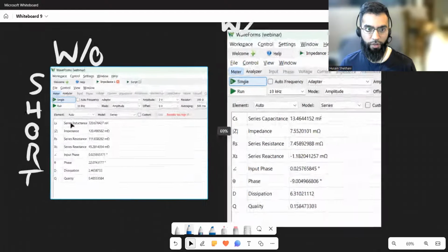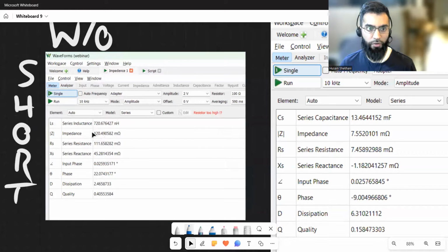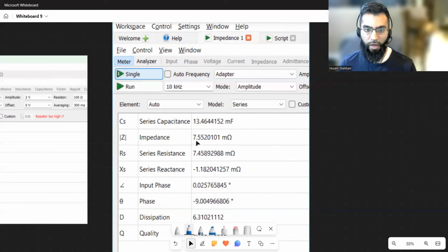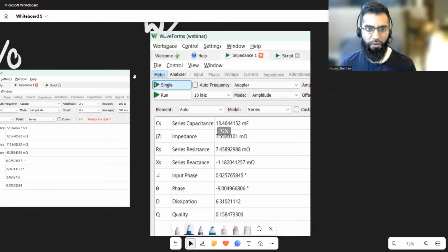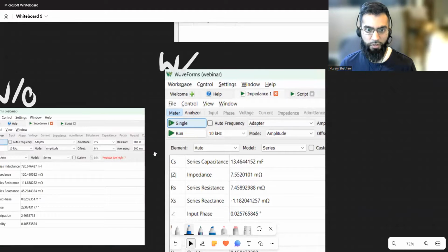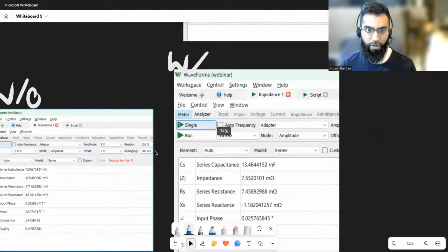Here I do the short circuit. With short circuit, without calibration, I'll just look at the impedance value. It's 120 milliohms of impedance, although the phase is 22 degrees. After calibration, it's 7.5 milliohms and 0.02 degrees. I don't remember, and this is set at 100 ohms. So this is all done at 100 ohms of that resistor value.